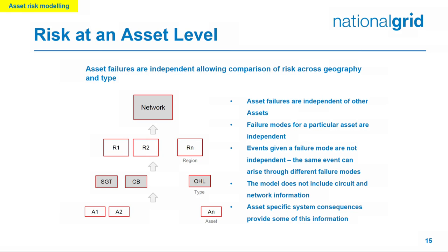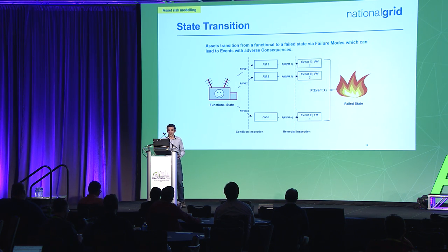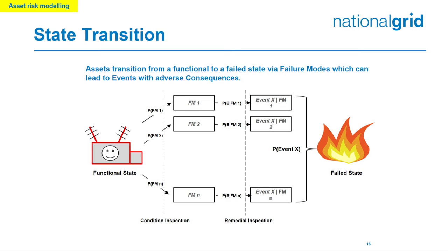So briefly, I'll talk about our risk framework — submitted and approved by our regulator last year, currently being implemented using Python, NumPy, and Pandas. Asset failures are independent of each other. A failure mode — something that can go wrong with an asset — is treated as independent. An event, which is a consequence of a failure mode, can arise through different failure modes. The model doesn't include circuit or network information; you've got assets at the bottom, you can bring that up to regions, then sum to get the network. An asset can move from a functional state through to a failed state by calculating the probabilities all the way through.